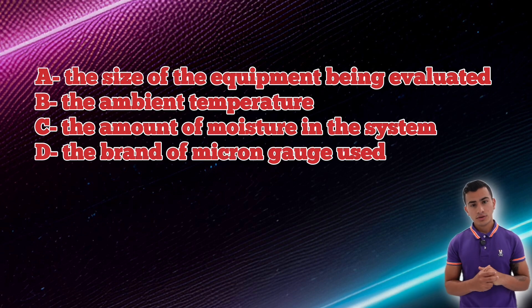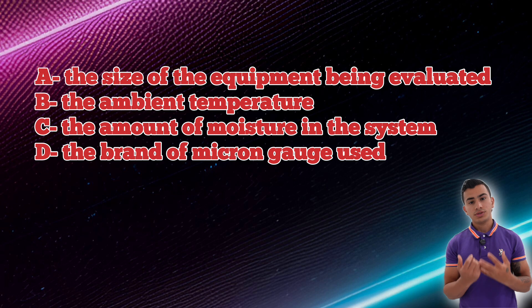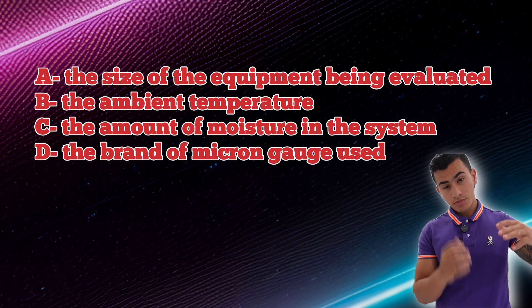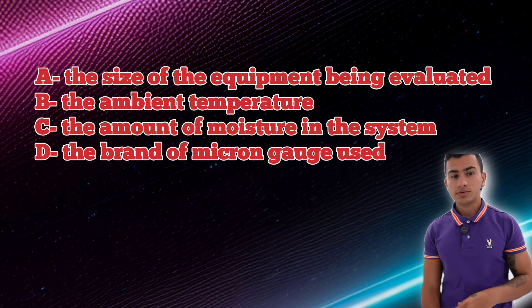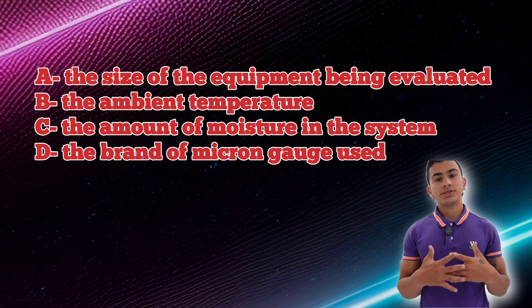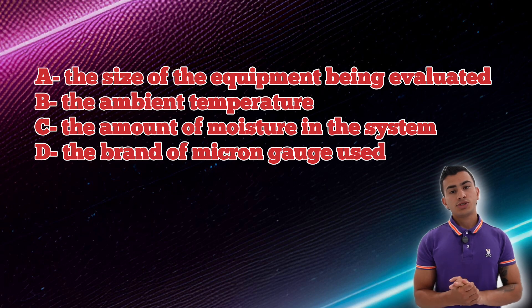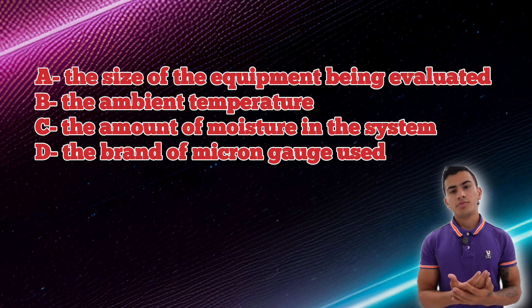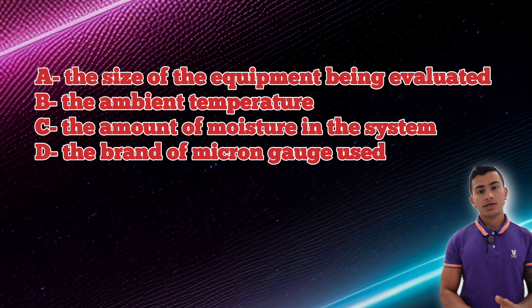Which factor does NOT affect the speed of recovery? The size of the equipment being evacuated — that will affect it, because the bigger the equipment, the longer it takes and the more refrigerant it has. Ambient temperature — yes, that affects it; if temperature goes up, pressure goes up. The amount of moisture in the system — that is the number one factor; if you have moisture, recovery speed is tremendously affected. The brand of micron gauge used — no, that will not affect it because it is just a brand. So the answer is the brand of micron gauge.